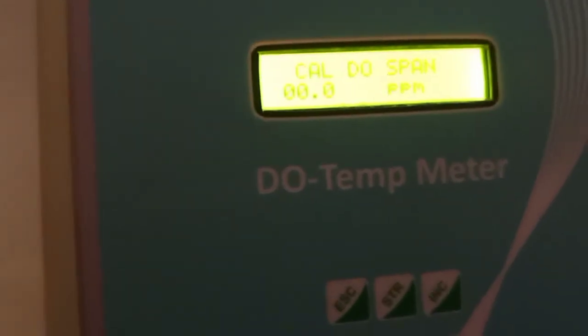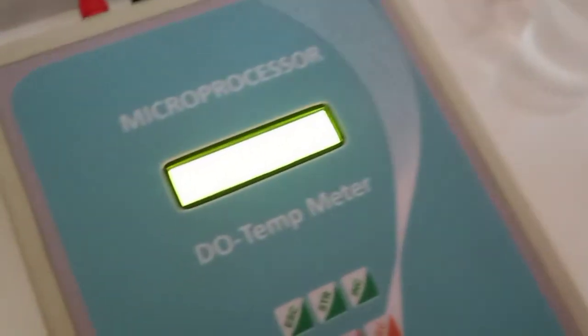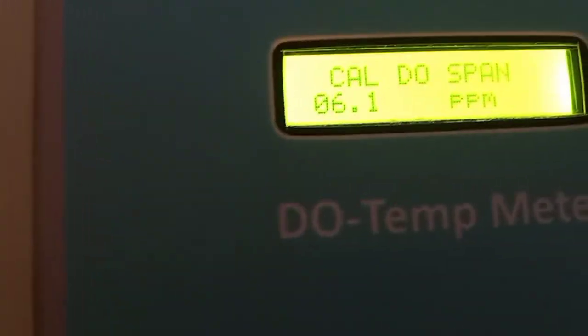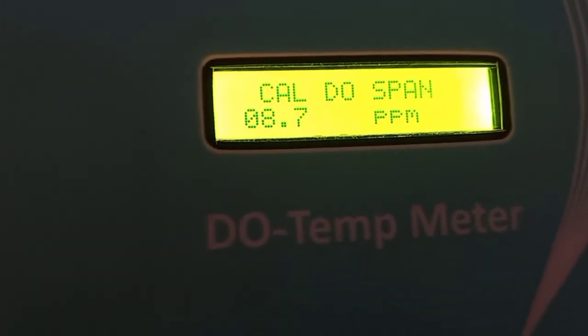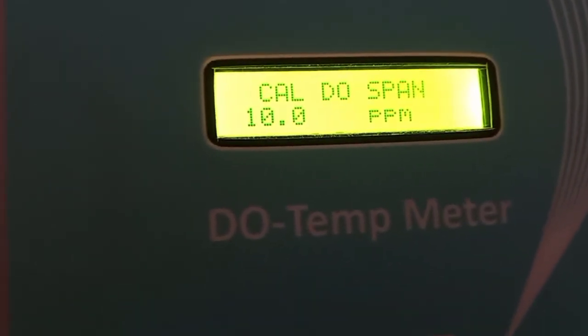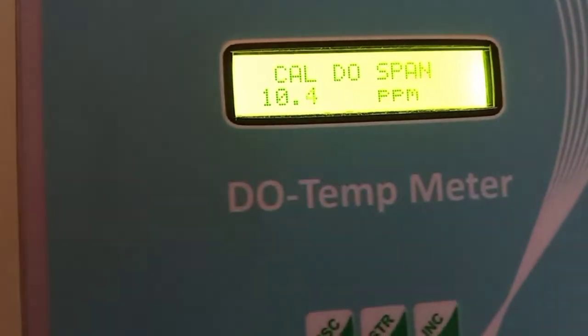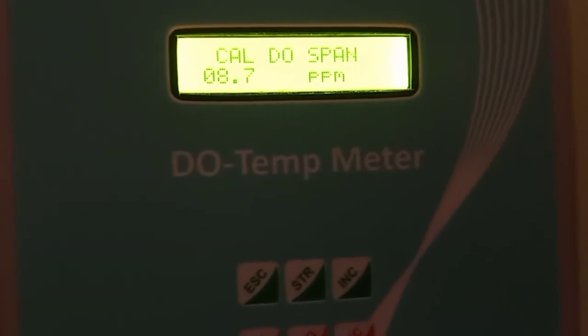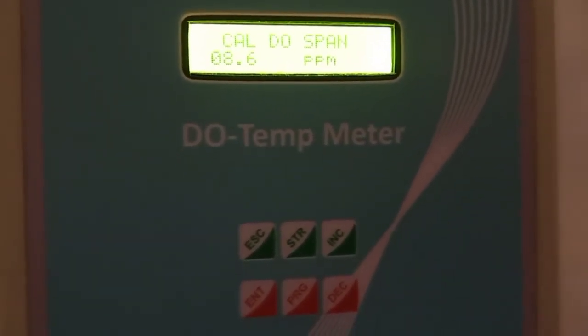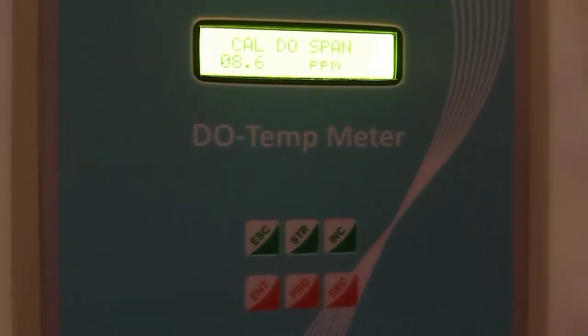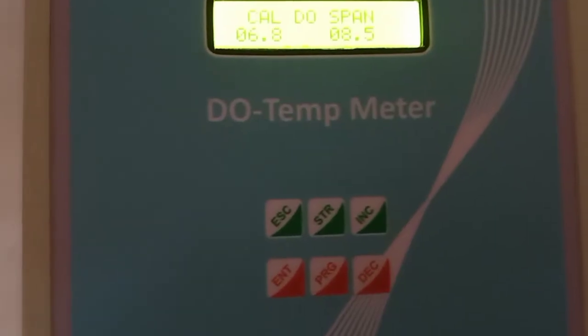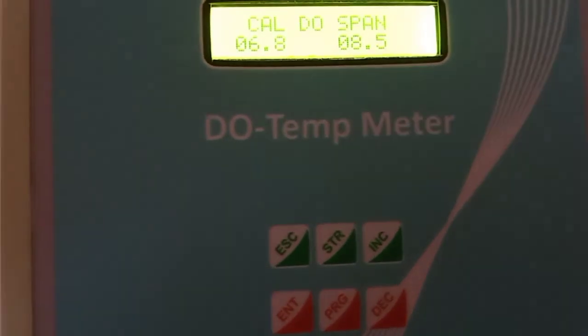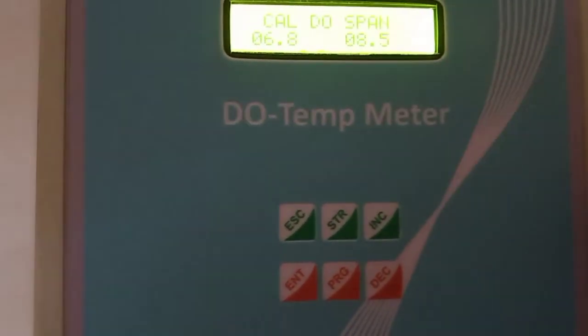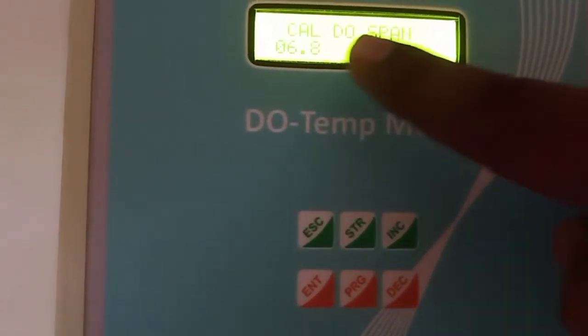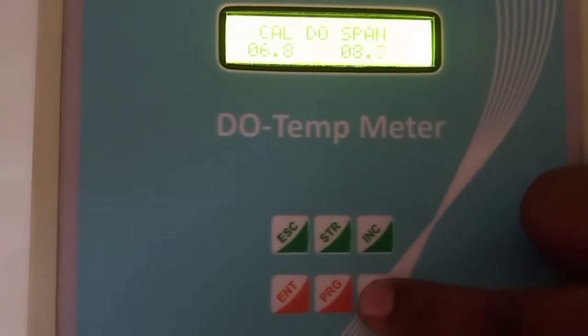Here span indicates saturated water. Wash the electrode thoroughly using distilled water and put the electrode into the raw water. Now the calibration process starts for the raw water. Wait for the stable reading. Once the readings are stable, press the enter key. After pressing the enter key, the display shows two readings like these. So using the increment and decrement buttons, match the two readings.